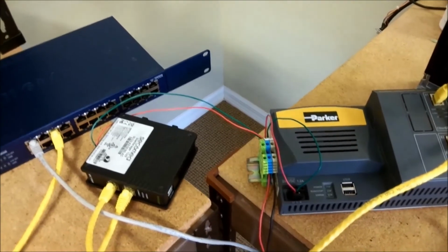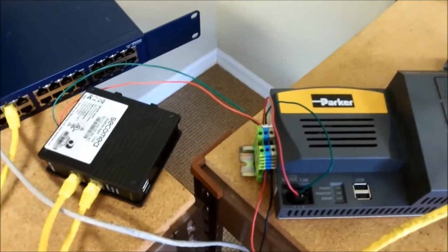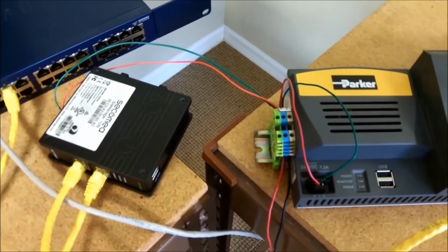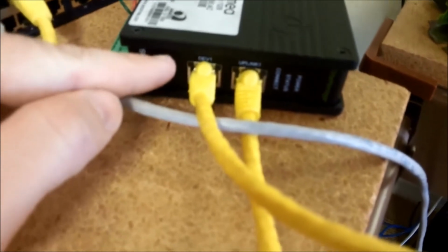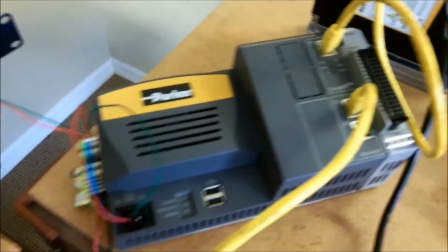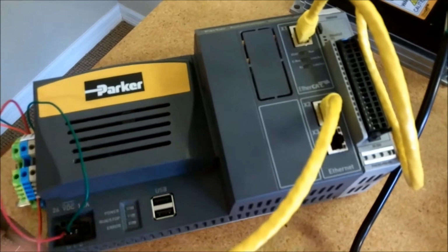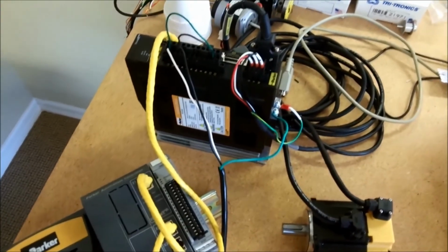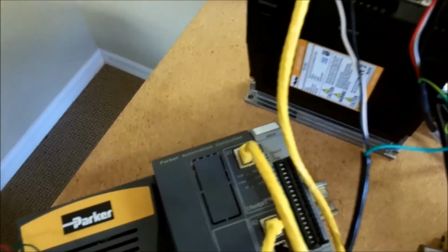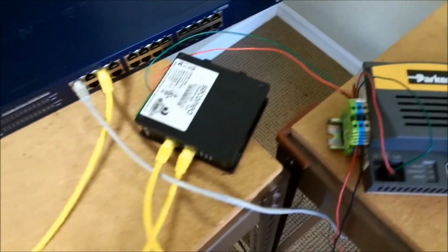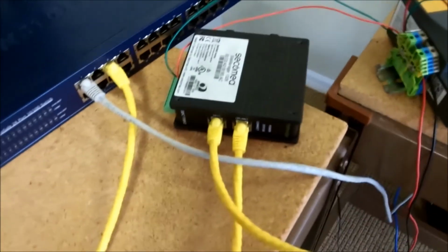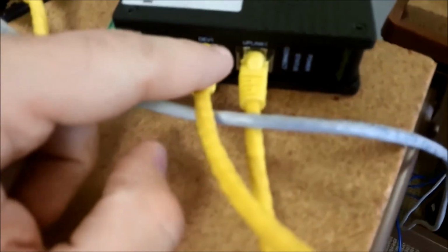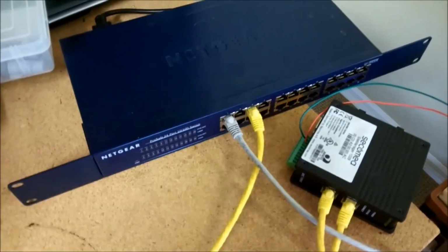First, we will hook up 24 volts to the Secomea Site Manager and the PAC controller. Next, we'll connect the Site Manager to the PAC via the Dev1 port or Device1 port of the Site Manager and the X2 terminal of the PAC controller. Then, we also have connected a Parker P-Series motor and drive connected to the EtherCAT port of the PAC controller. Finally, we connect the Secomea Site Manager to our local area network via the Uplink 1 port here that goes to this switch and then to our local area network.